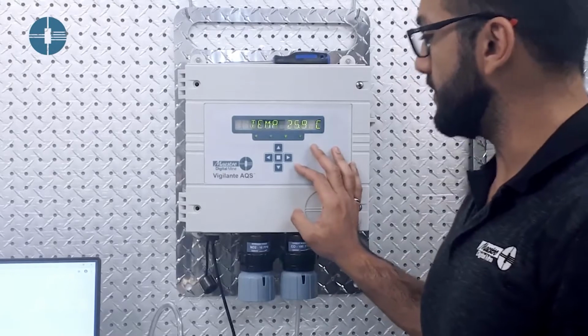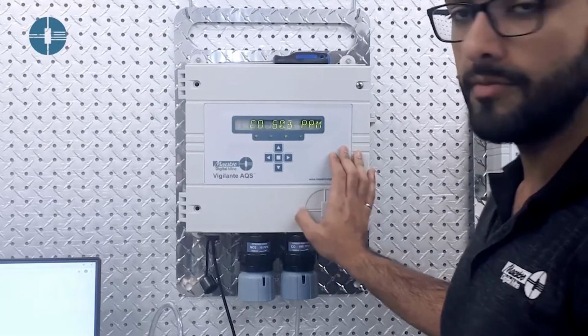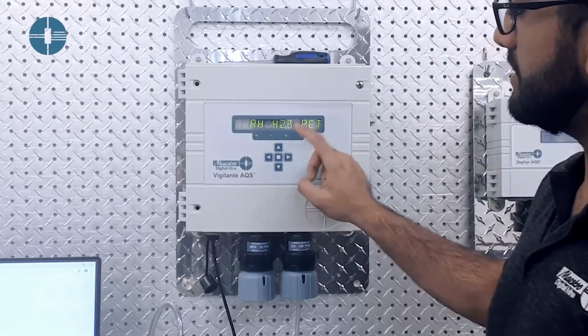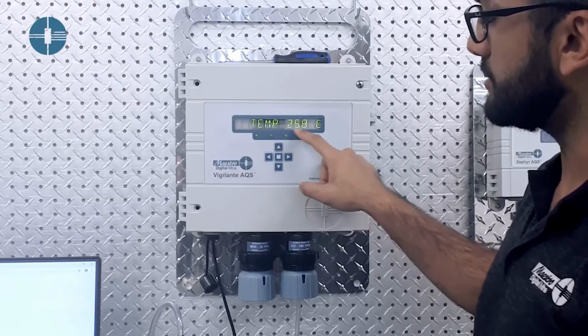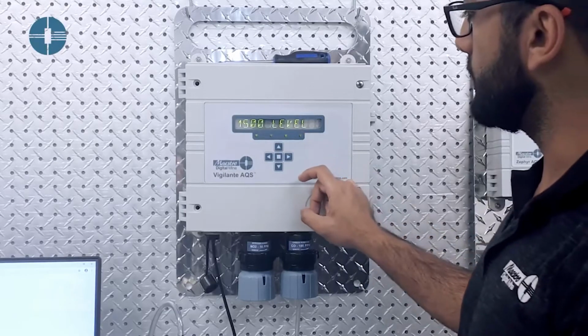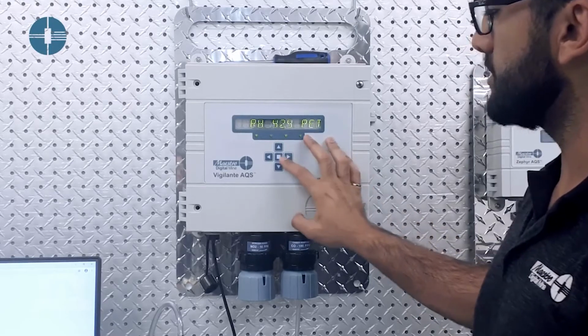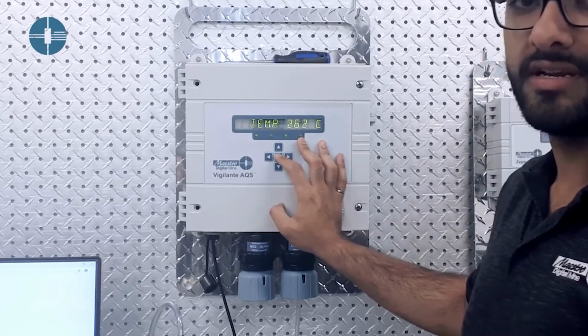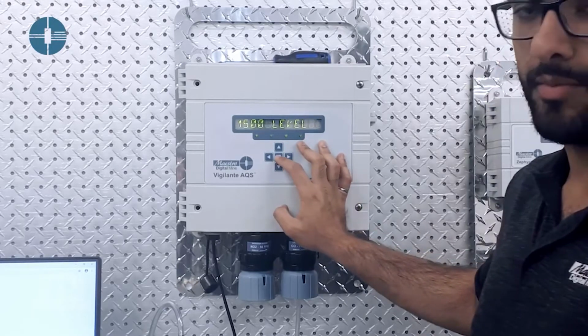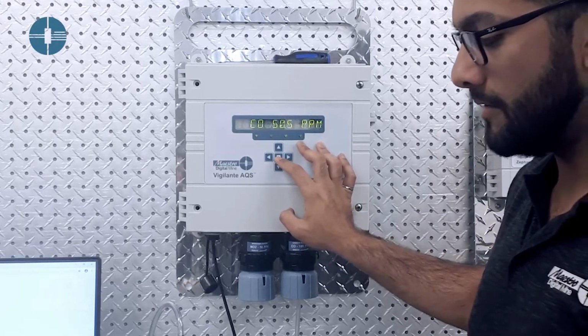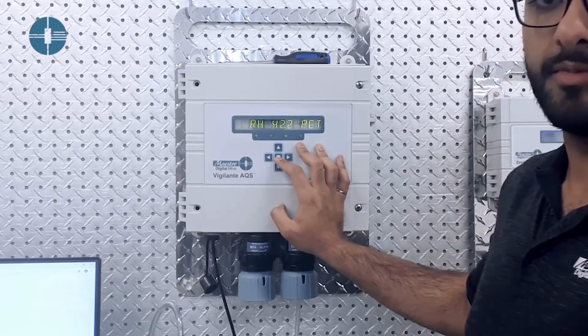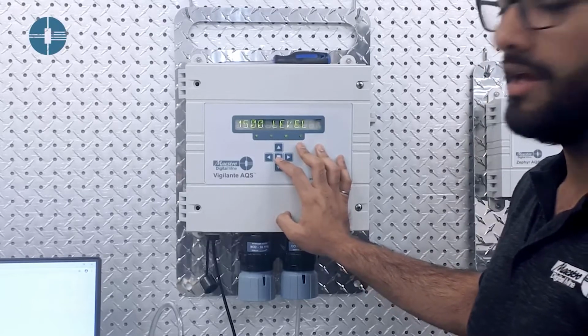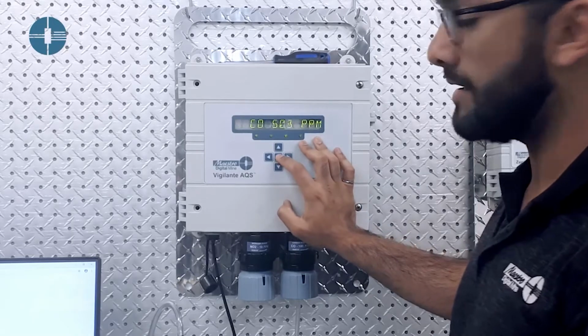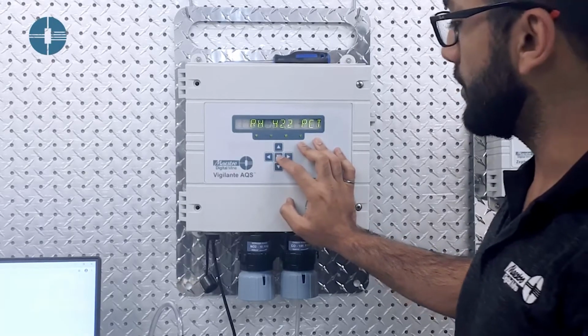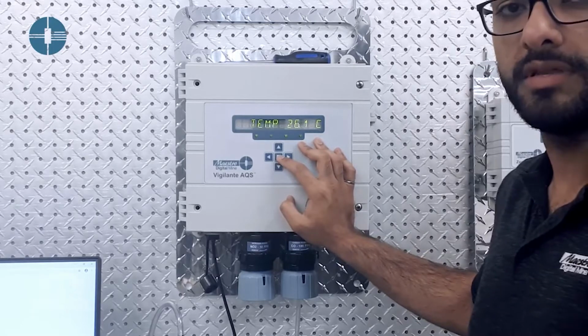So after our 3 minutes, we're going to come to our station over here, and a good confirmation to show you that the gas sensor is actually reading. You'll see that there's an actual CO reading that will pop up over here. There you go, 50, which is a good indicator that the sensor is now saturated at a 3 minute mark, and it's time to calibrate as well. The recommended method is to use an actual timer and make sure that when you hit the 3 minute mark is when you start going through saving the calibration over here. So we're going to repeat the same steps as we did for the zero cal.